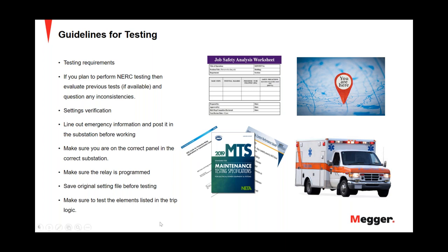We also want to make sure that when we do our tests, we're testing the elements that are in the trip logic. A lot of times there's conversation about this. If the elements in the logic are not enabled, testing the logic isn't really going to do much good. Conversely, if I have elements that are enabled but the logic portion doesn't have those elements in it, those aren't going to do any good either. It's always nice to know what the relay is going to operate on.